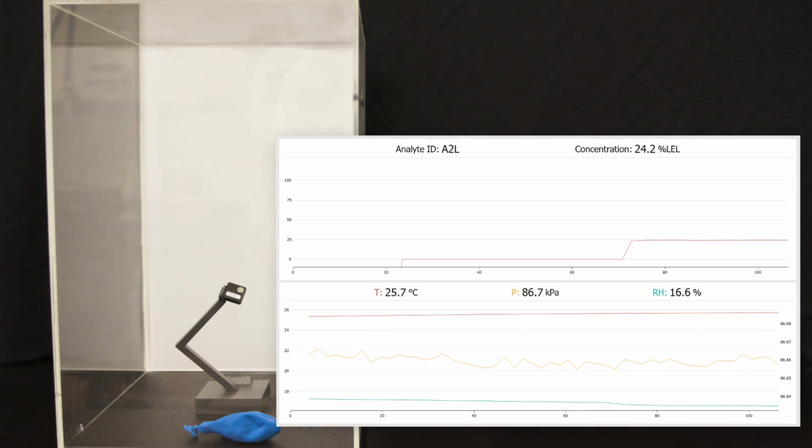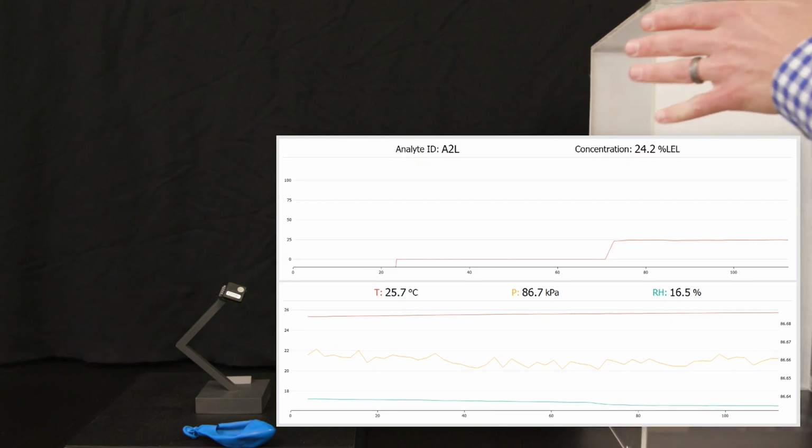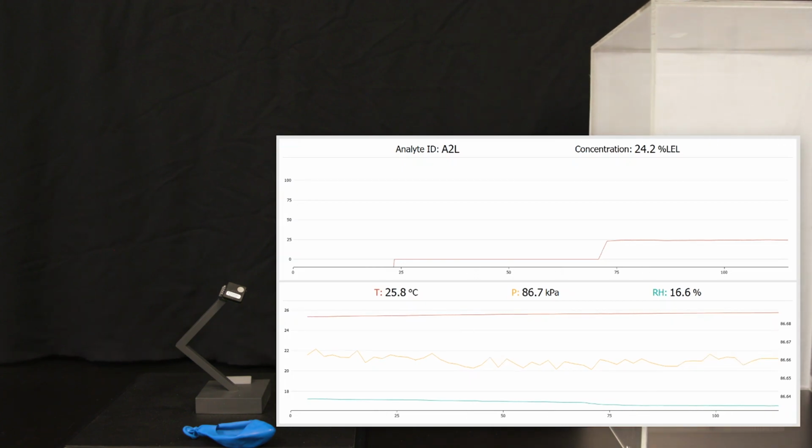And then we can go ahead and pull the lid off here. And you'll see the sensor clear out from R32 quite quickly. This is one of the fastest responses you'll find in the industry. You'll find that many other technologies are in the, say, 20-second range. We know that the UL standard requires a less than 10-second response time. So for many of those sensors, they'll be required to drop their set points, which will potentially lead to issues with false positives.